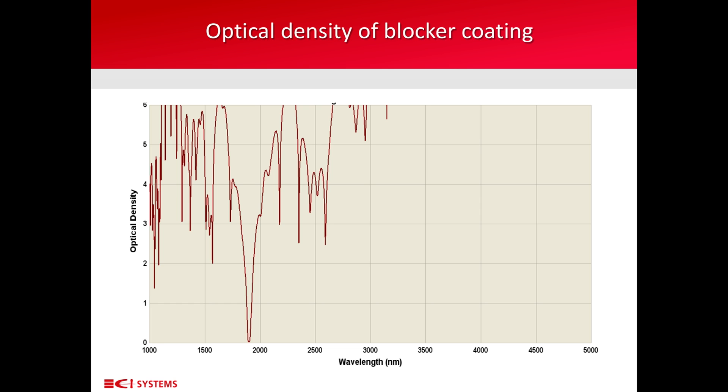It's very low because the transmittance is very high. But outside the range of about 1,800 to 2,000 nanometers, the optical density is very high, even three orders of magnitude higher than at the peak wavelength. This means that the transmittance outside that region is very low, down to the order of a tenth of a percent. So, this shows how the blocker filter works.